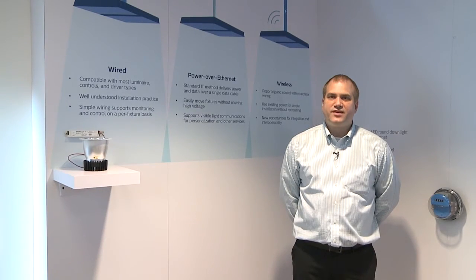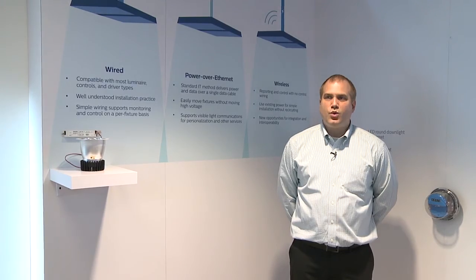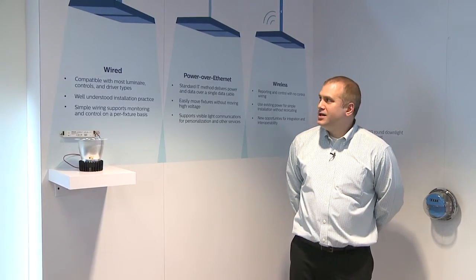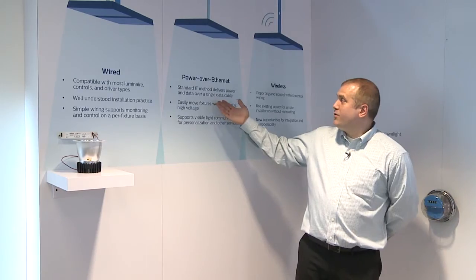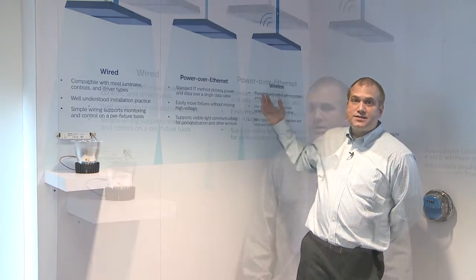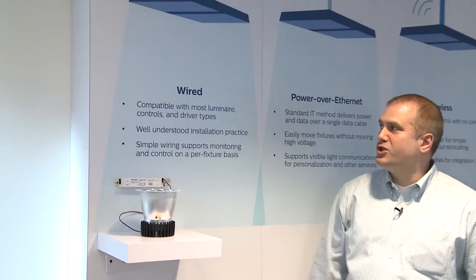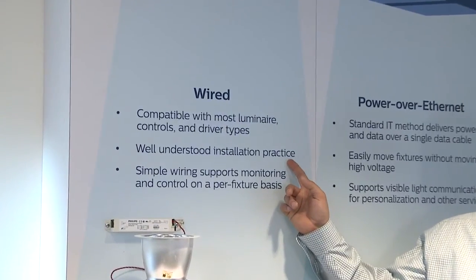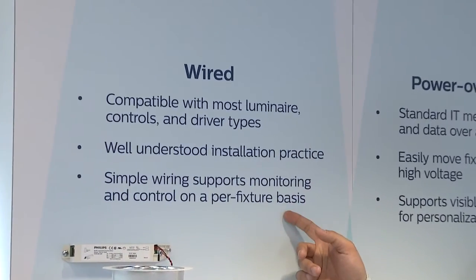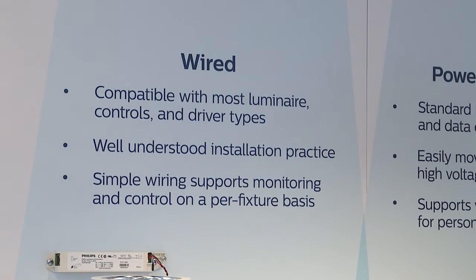One of the advantages of the Philips Envision Manager system is that we're not tied to one architecture to connect lights. We can connect lights via wired, Power over Ethernet, and wireless. The wired architecture allows compatibility with the most luminaires, controls, and drivers. It's a well-understood installation practice and allows for simple wiring, and supports monitoring and control on a per-fixture basis.